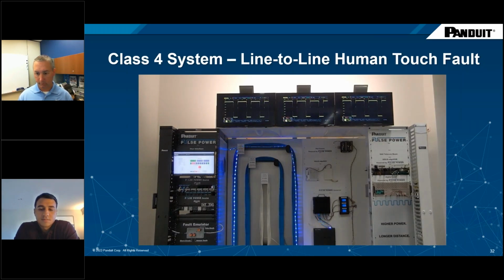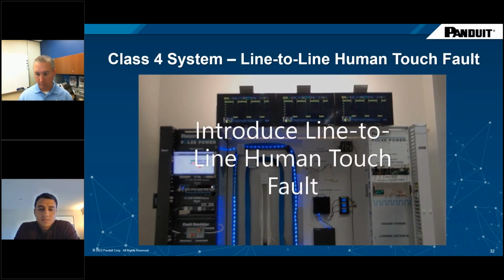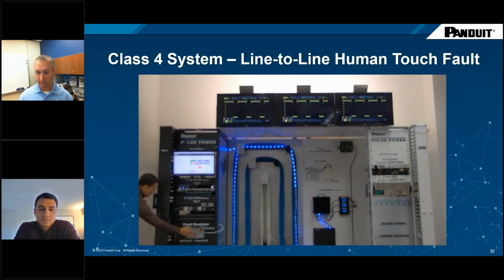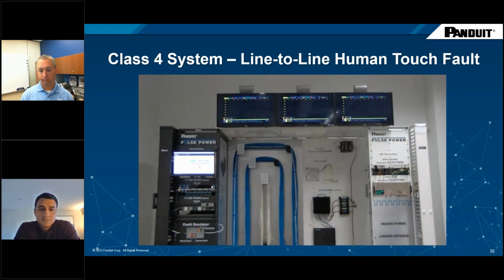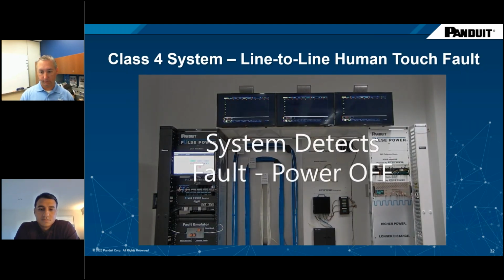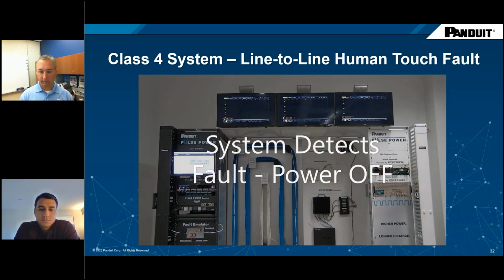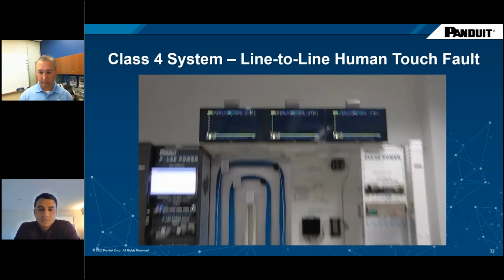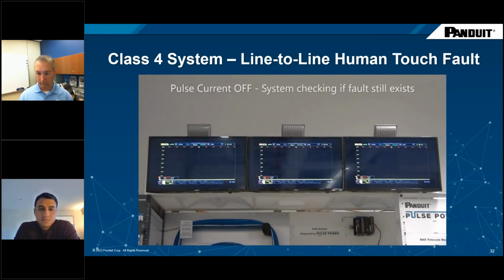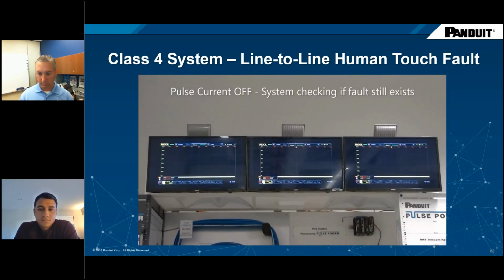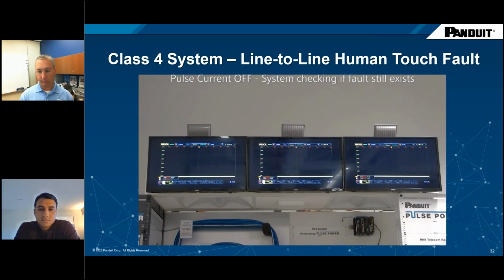Now we can go ahead and introduce the line-to-line human touch fault by pressing that button on the fault emulator box. What just happened is that the Class 4 system detected that fault and turned power off almost instantly. You can see that there's no pulse current flowing through that cable anymore. And now the system is checking if that fault is clear.